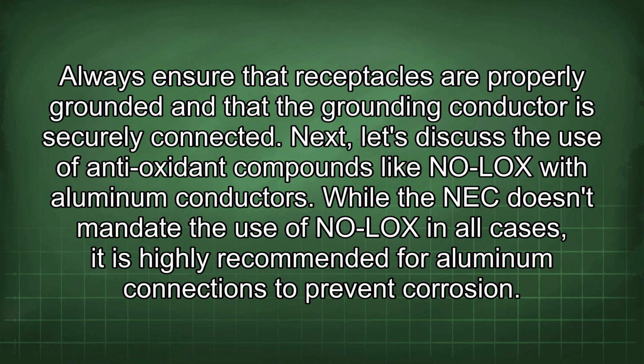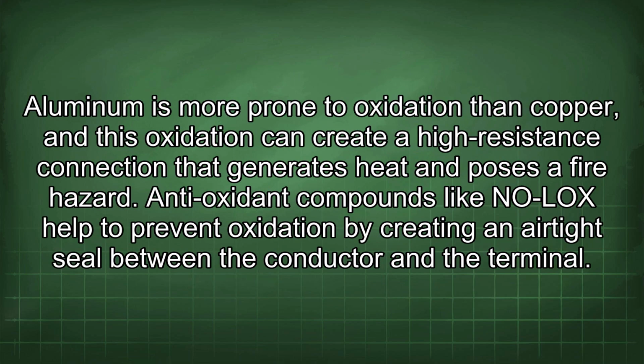Next, let's discuss the use of antioxidant compounds like NO-LOX with aluminum conductors. While the NEC doesn't mandate the use of NO-LOX in all cases, it is highly recommended for aluminum connections to prevent corrosion. Aluminum is more prone to oxidation than copper, and this oxidation can create a high resistance connection that generates heat and poses a fire hazard.